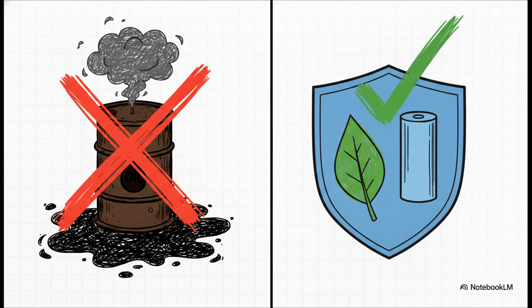Back in the day, heavy circuit breakers usually used flammable oils or this incredibly potent greenhouse gas called SF6 just to quench electrical arcs. VCBs don't need any of that. Because they use a pure vacuum, there's literally no oil to catch on fire and no toxic gas to leak out into the atmosphere. This makes them incredibly eco-friendly, remarkably safe, and highly reliable. Plus, without oil or gas to constantly replace, maintenance costs drop significantly.